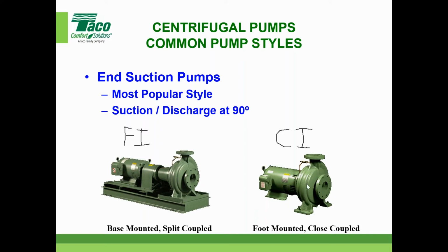Over here, if you have to get at the seal, you have to take the motor out, and the motors get heavy, right? That's a fact, Jack. We sell these up to 60 horse, as do other pump manufacturers, because it's a JM style motor. But I wouldn't necessarily do too many that size.